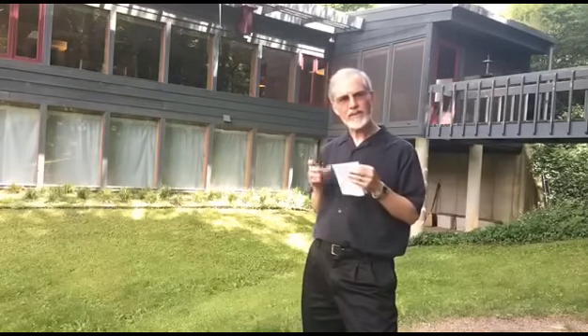Now, it was really neat that Brett and his team did the energy assessment with the blower door. This is not particularly a tight house. I was a carpenter with not tremendous skills. Doors and windows used to be leakier. So it is not a particularly tight house, and it still performs that well.